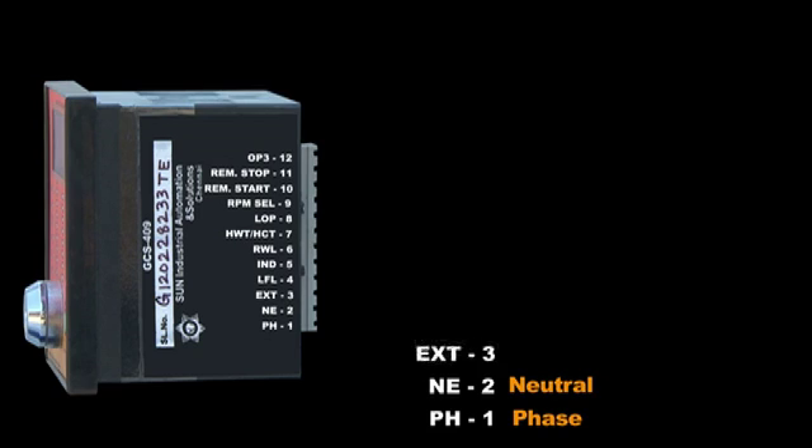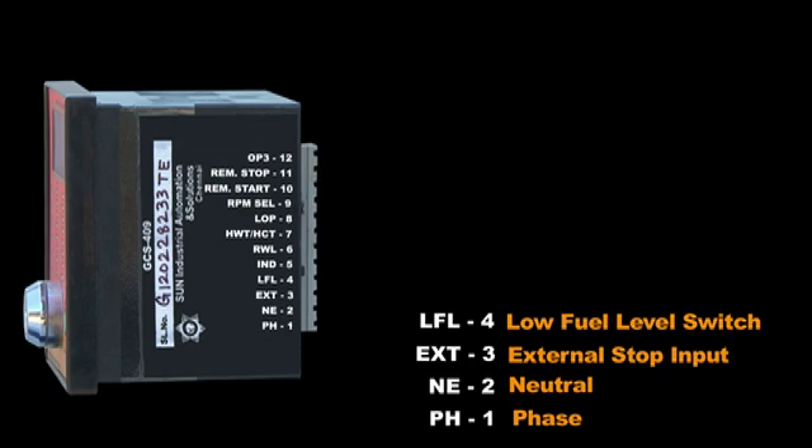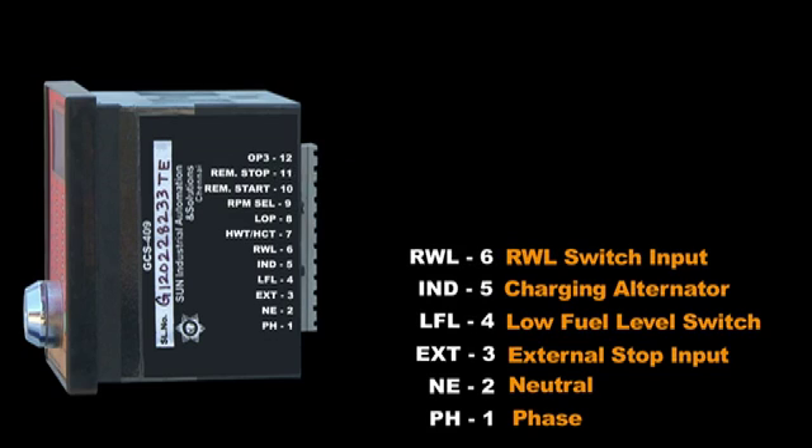Terminal 1: Phase. Terminal 2: Neutral. Terminals 1 and 2 are connected to the main alternator output for sensing the RPM. Terminal 3: external stop input. Terminal 4: low fuel level switch input. Terminal 5: charging alternator. Terminal 6: radiator water level switch input.